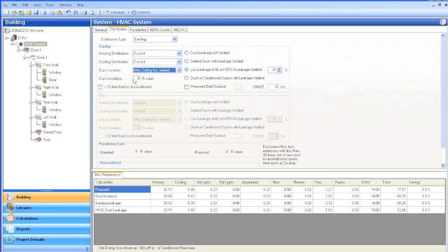Duct insulation on the ductwork, that goes in this box here. If you have a situation where you have different levels of duct insulation, especially in an existing home, then you are asked to average it. So come up with the average value that it would apply to all of the ductwork. Previously, we had advised people to use the measured duct surface menu. We actually are no longer requesting that of contractors, and it is our recommendation that you just put in the average duct insulation value here.